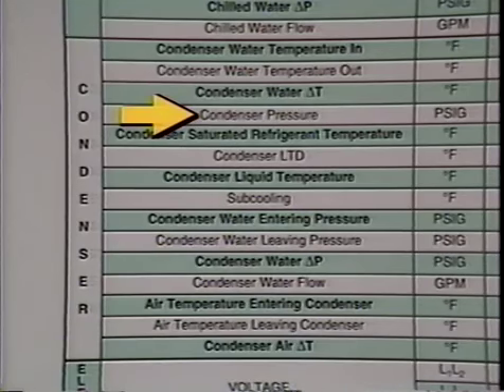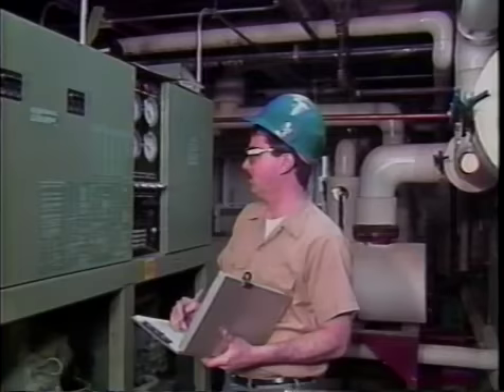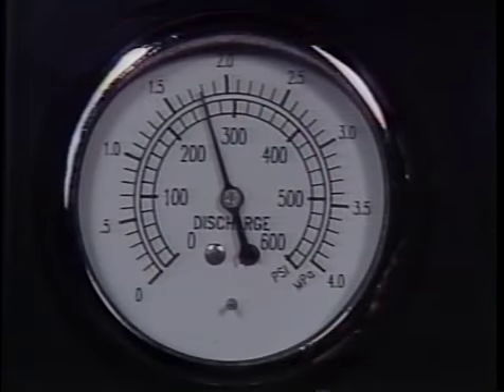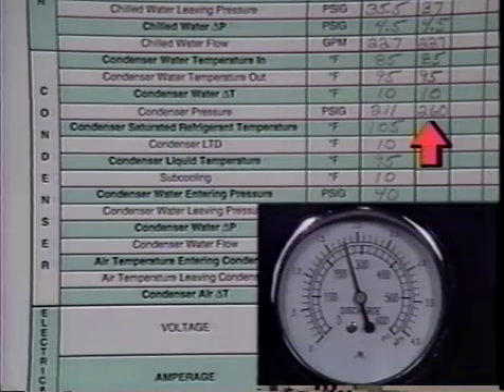Condenser pressure. Record the condenser pressure. With design water temperature and water flow through the condenser tubes and operating at full heat load conditions, this pressure should not exceed maximum design condenser pressure. When condenser pressure is higher than design, it's an indication that the chiller is operating inefficiently.